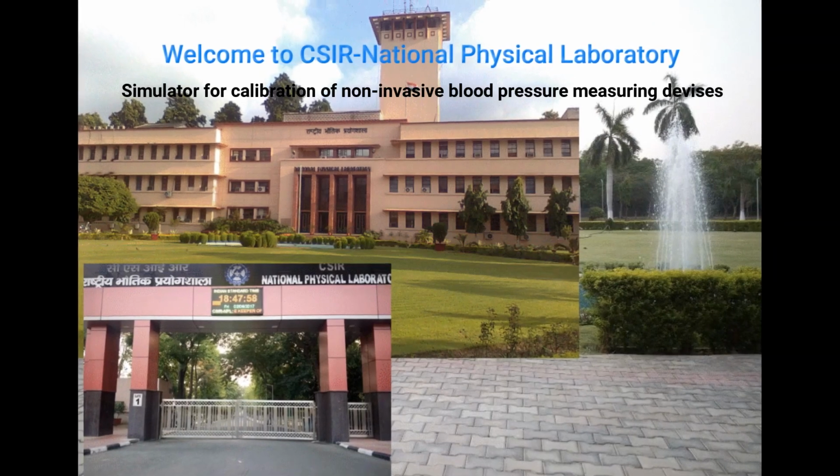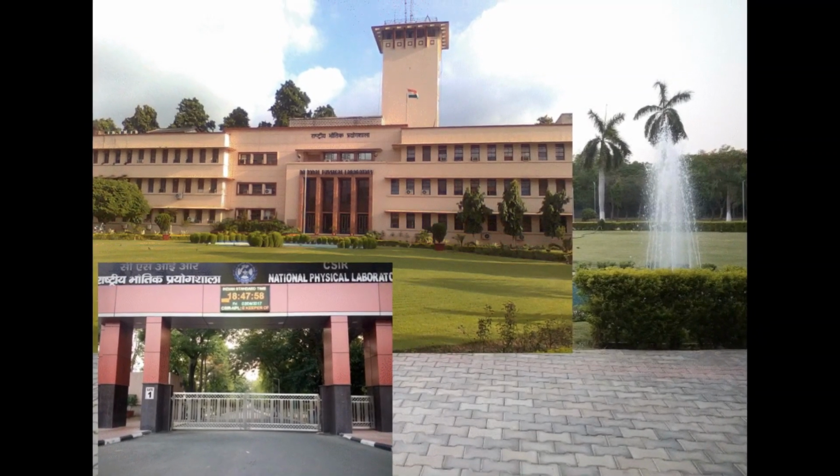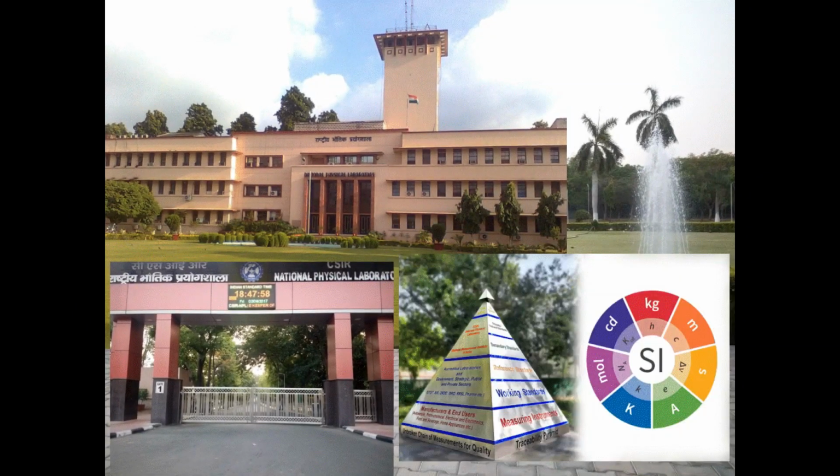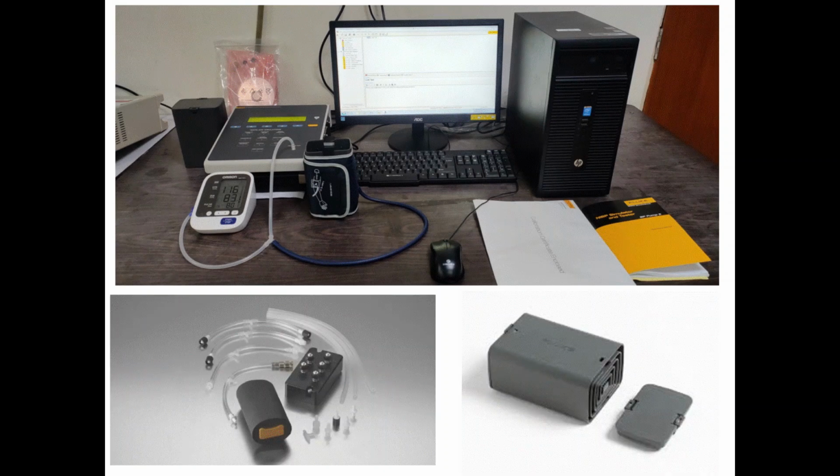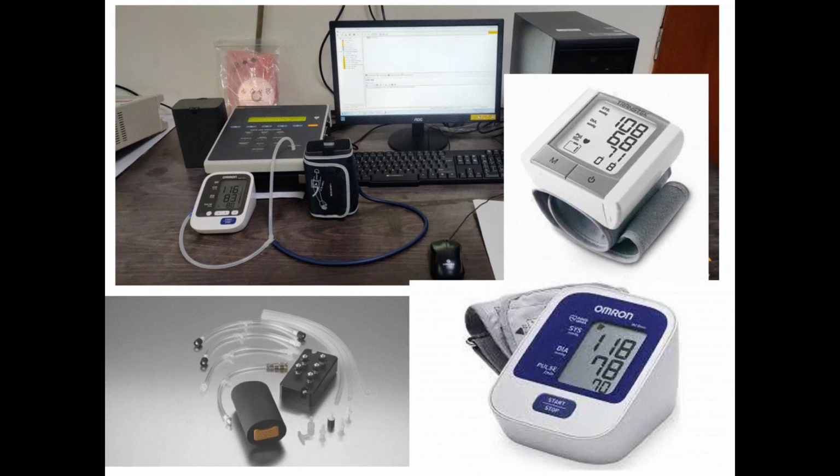CSIR, National Physical Laboratory, also known as the National Metrology Institute of India, has set up a state-of-the-art facility, blood pressure simulator and test bench to test and type approval of automatic and analog non-invasive blood pressure devices. An accurate blood pressure measuring device helps in diagnosing heart, kidney and other vital human organ related problems.